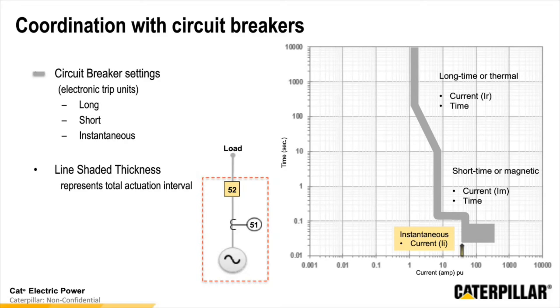The importance to understand here is that we don't want to overlap those shaded regions as we're looking at our different protective zones, because if we were to overlap the different shaded regions, we could end up tripping one breaker out of turn because one operated faster than the other one did on that specific application. Even though we thought that one should have started operating faster, maybe the other one was able to respond quicker to the fault. So we want to make sure that we're not overlapping those regions overall.